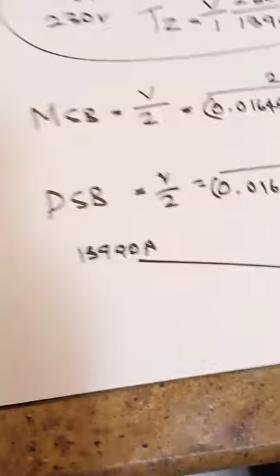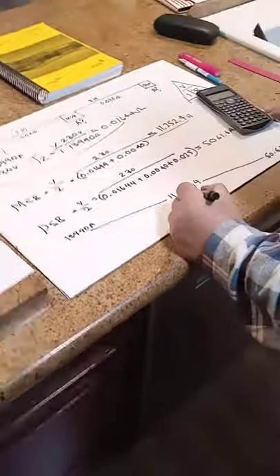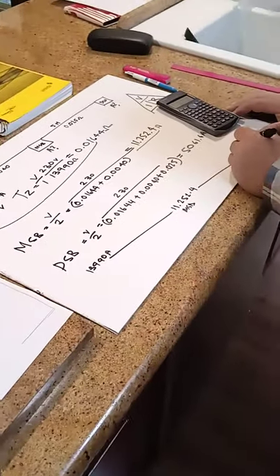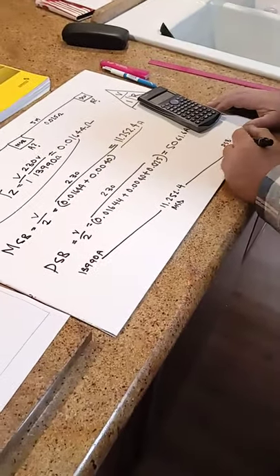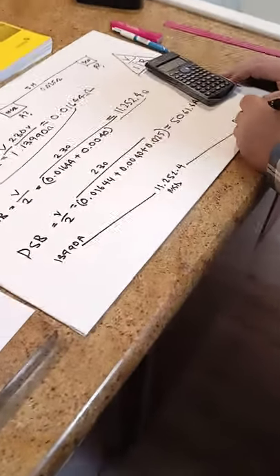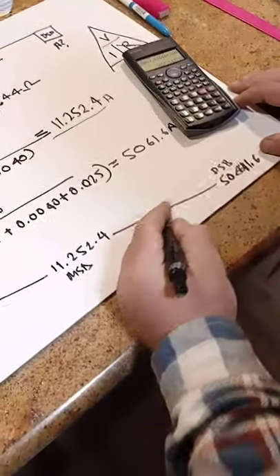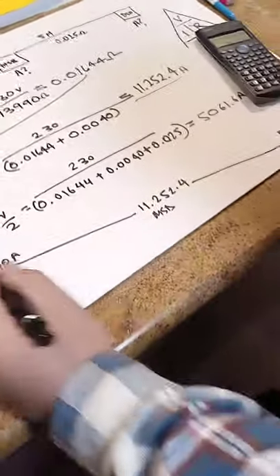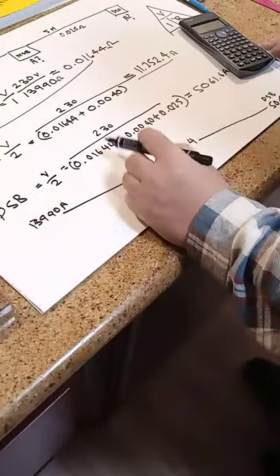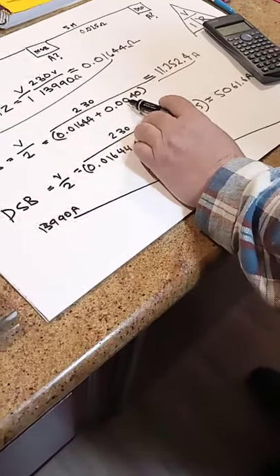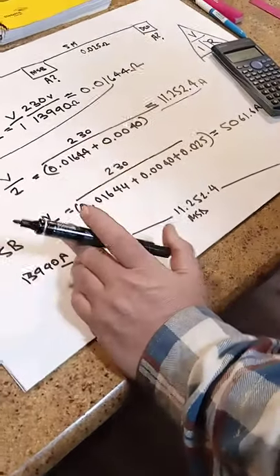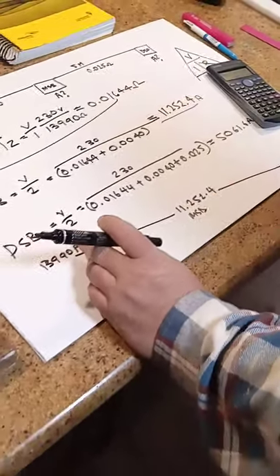At the end of the day, what I'm going to show you is as we get further away from the transformer, this is my main switchboard and this is the distribution board, we actually get less fault current. So the current has actually dropped as we got further away. Depending on how the values are set up, if you have an extra zero or a decimal point down, it'll actually make the current drop down quite further.